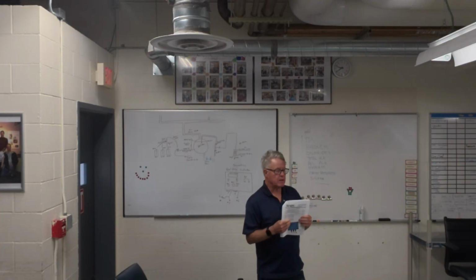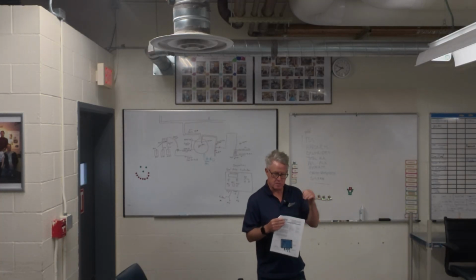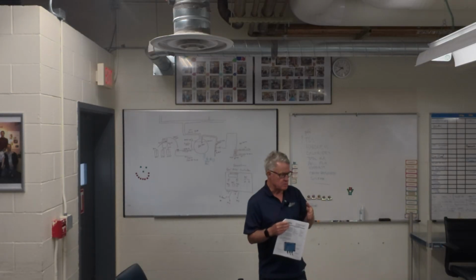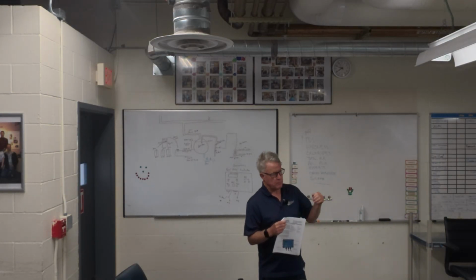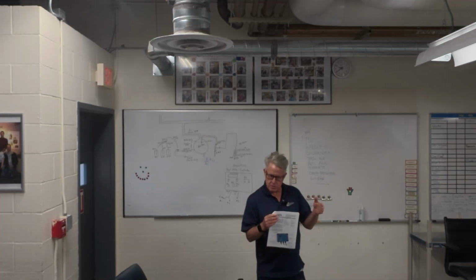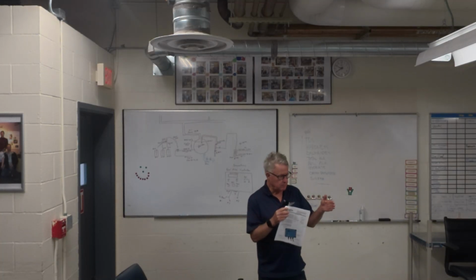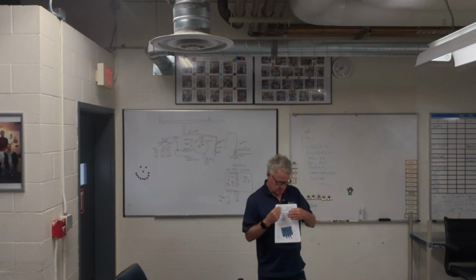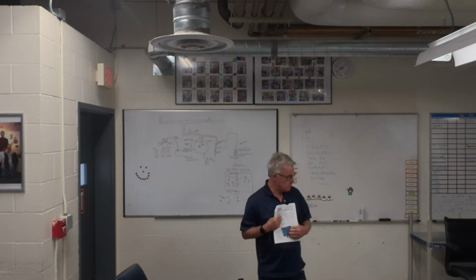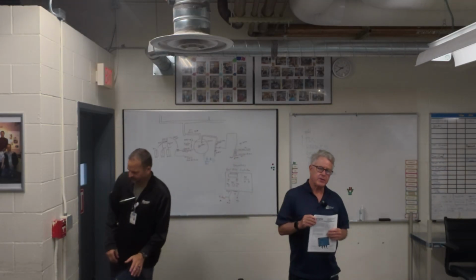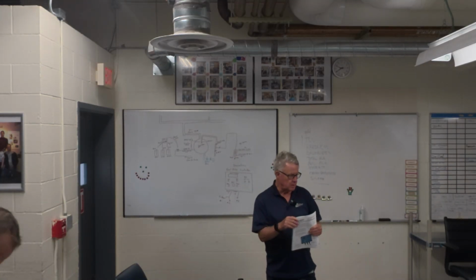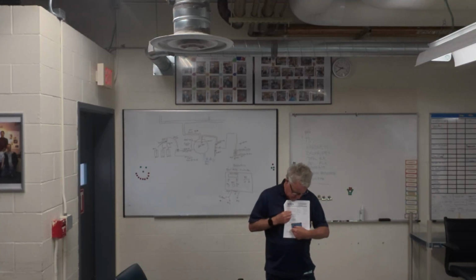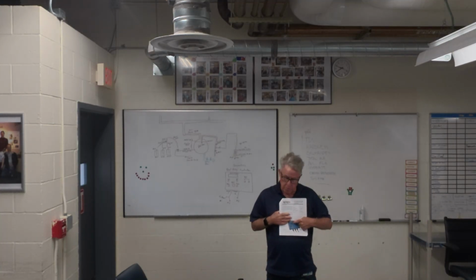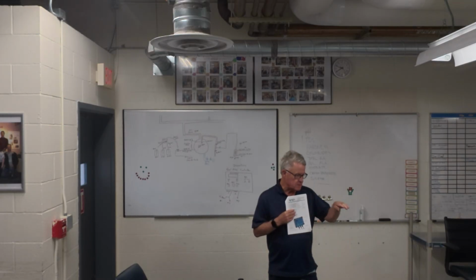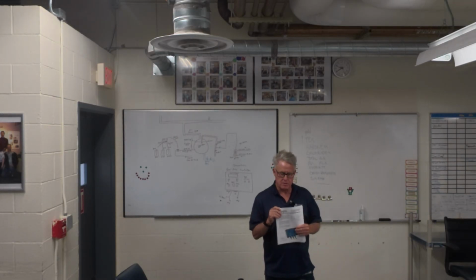So as we get going here, that's one of the common errors you'll start to see. As we lock these down, you might get what's known as an OUF reading on them. We can offset the accumulations a little bit so they're not sequencing at the same time, and we can increase the pumps for the moments that one or two are on. So we'll have to manage that early on in the equation with you guys. But that's the most common troubleshooting error I think you're going to engage here. And it's going to show up on that part right there where you see the accumulation, there's 0. That'll read OUF. Again, it's covered in the manual here, but that's essentially what it's saying.